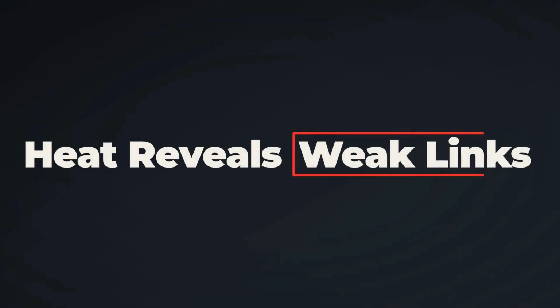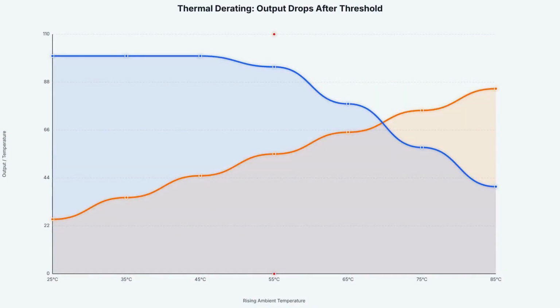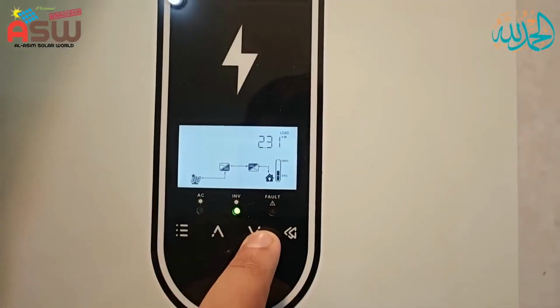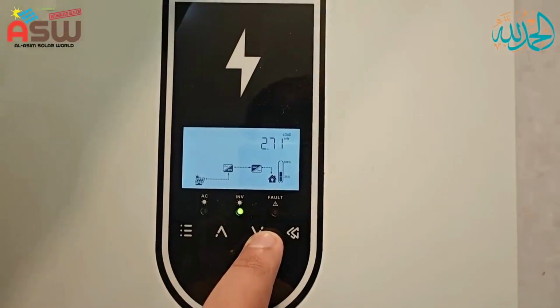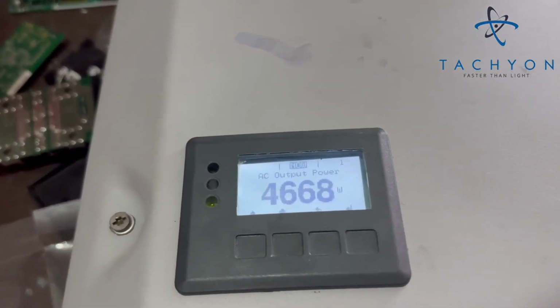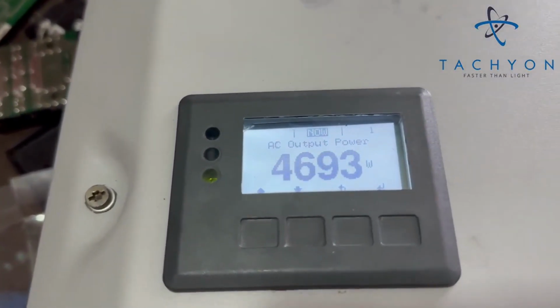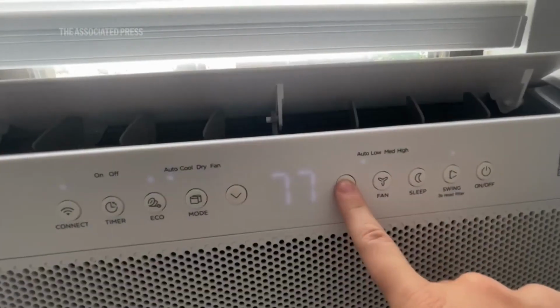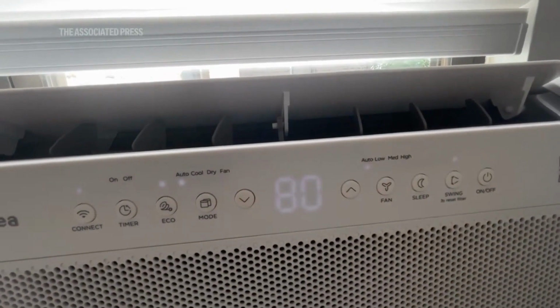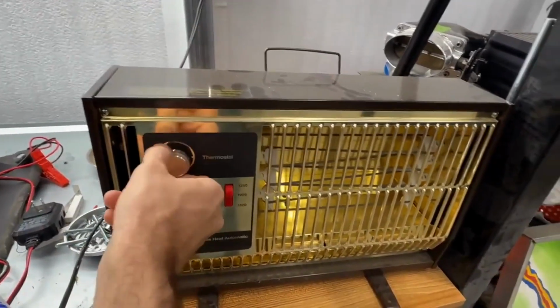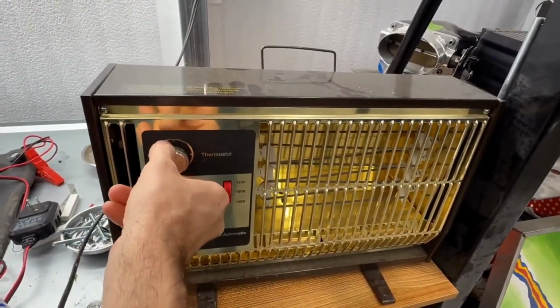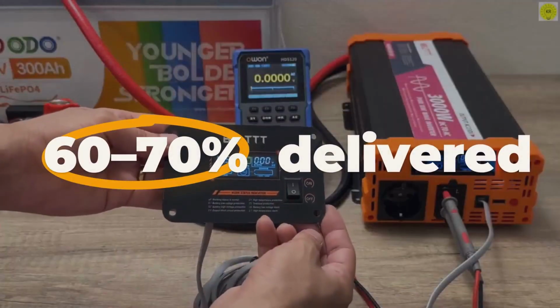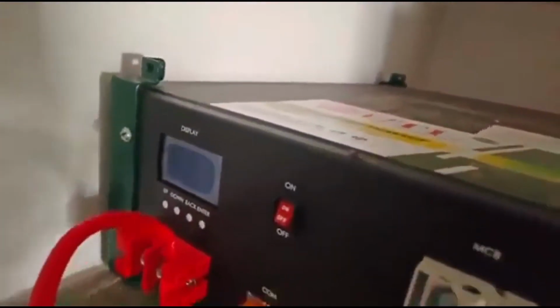Here is the specific mechanism that exposes undersized designs. It is called thermal derating. When internal temperatures climb past a threshold, the inverter automatically cuts output to protect itself. That sounds responsible until you realize the cut happens at exactly the moment demand is highest. A summer afternoon, full air conditioning load, battery cycling hard. The inverter is not failing visibly. It is just quietly delivering 60 or 70% of what the homeowner paid for during the hours that matter most.